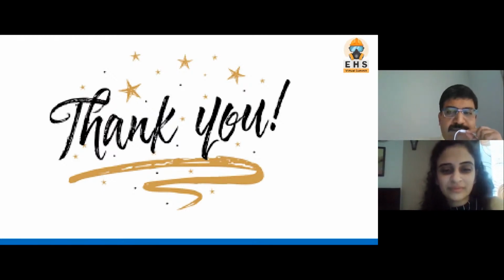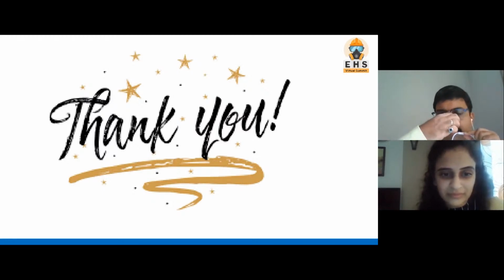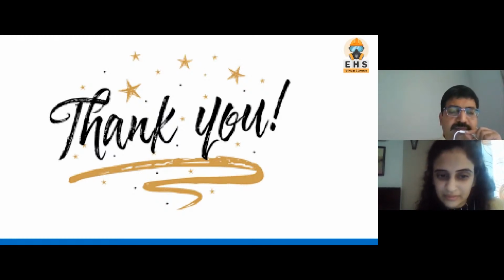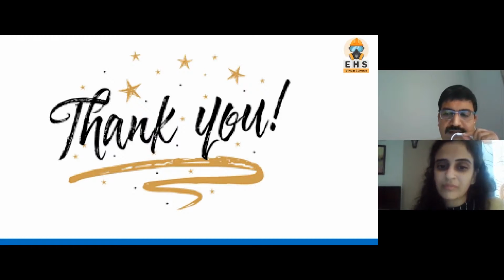For everything, maintenance is required—it is not only about the fire protection system. Everywhere maintenance is very important. Normally maintenance doesn't mean we need to open and clean it. If you see the entire water-based fire protection system, it is always charged with water, and the pressure gauge always shows that pressure. It is always charged, but theoretically it should be charged—practically we should check whether it is normal, whether the pumps are okay, because ultimately the heart of every fire protection system is the fire pumps. If the pumps are not working, then it is of no use. So I will not say directly maintenance, but regular checking of the system and whatever minor servicing is required should always be there.